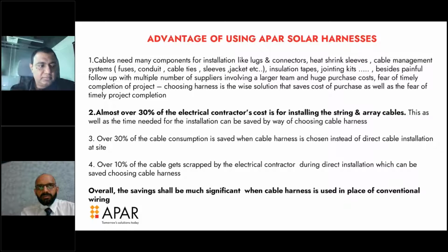So we have done an extensive study on this, and we have found that nearly 30% of the contractor's cost is spent in installing the string and array cables, and also the time that is needed for that. This can actually be saved by using cable harnesses. So what Apar does is, we are able to offer these harnesses as well, not just the cables. The cable consumption is also reduced by nearly 30% when a harness is used instead of direct cable installation. Generally 10% of the cable gets scrapped because of direct cable installation, which can be saved by using cable harnesses. So rather than conventional wiring, solar harnesses can result in a huge saving for the contractor, the EPCs, or even directly.